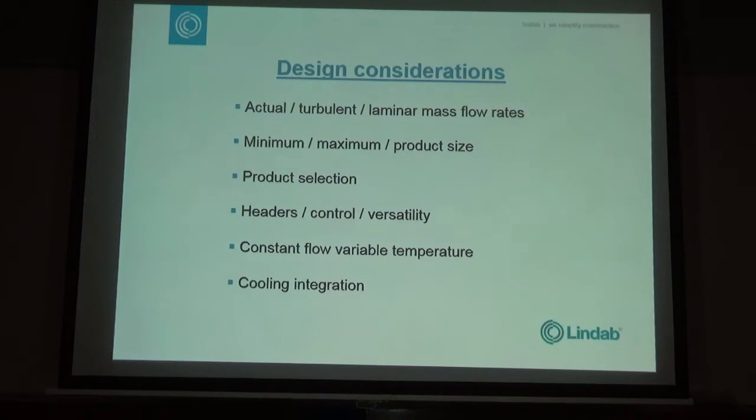problems I seem to encounter with radiant panel systems is that people don't put enough water through them. So you must always have turbulent flow. You must always have a Reynolds number of 6,000 going through your radiant panel to get turbulent flow. Otherwise, if it's laminar, you don't get 100% of the heat transfer from your water. So to show you how important that is, we like at the moment to design at a 20 degree delta T.